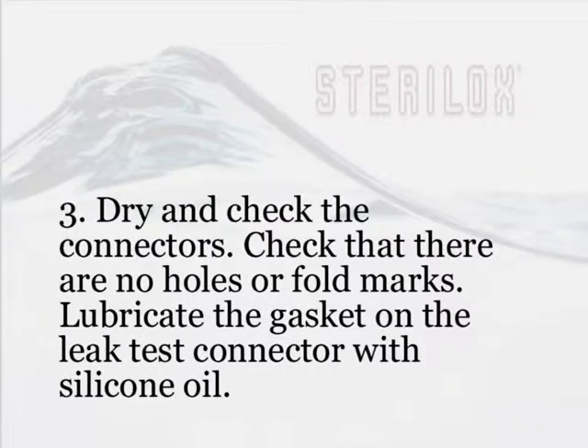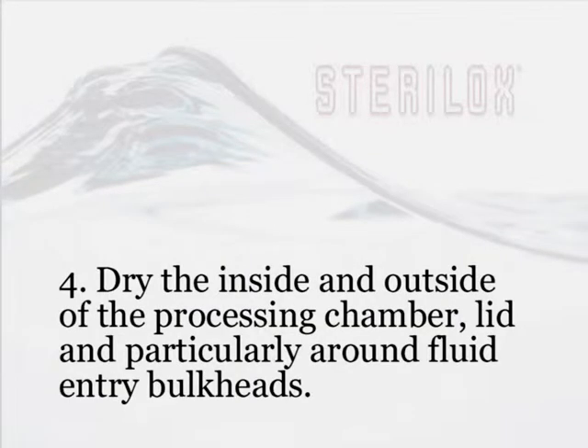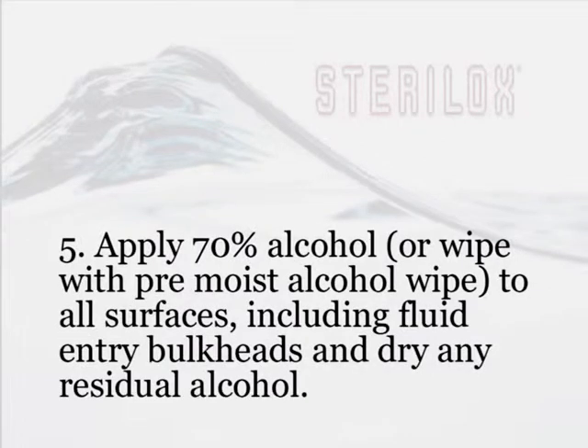3. Dry and check the connectors. Check that there are no holes or fold marks. Lubricate the gasket on the leak test connector with silicone oil. 4. Dry the inside and outside of the processing chamber, lid and particularly around fluid entry bulkheads. 5. Apply 70% alcohol or wipe with pre-moist alcohol wipe to all surfaces, including fluid entry bulkheads, and dry any residual alcohol.